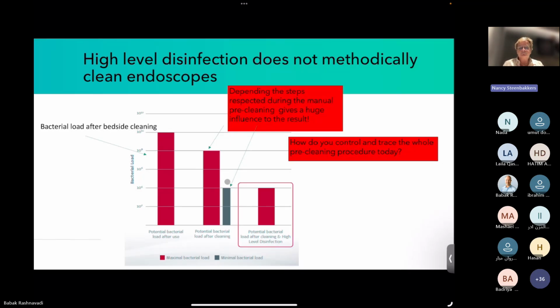But here she wanted to improve that. When you put the gray bar as a result in the washer disinfector, it will not minimize the bacterial load anymore. So that means that the full focus has to be on the cleaning. The pre-cleaning in your sink is the most important step of the whole procedure of your endoscope. This is something that you really have to understand, because a lot of people are relying on the washer disinfector because it's a disinfection cycle, but the cleaning cycle in a washer disinfector is way too short to do it all in a good way. That's why Dr. Michelle Alpha found out that the washer disinfector has its limits. That's why she says you have to go more and more to the manual pre-cleaning in a good way.